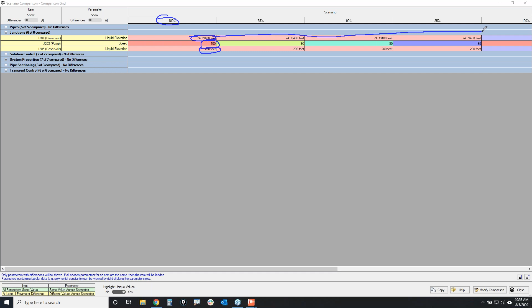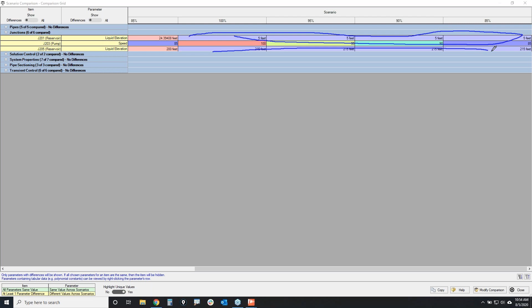Now that I have everything filtered, I can focus on what the values are in different scenarios. As I go along here, I can see that in my 100% speed scenario, here's my regular liquid surface elevation, and then my pump is at 100% speed. All of these have the same liquid elevation for supply and discharge, but you can see by the different colors that it's the pump speed that has changed.